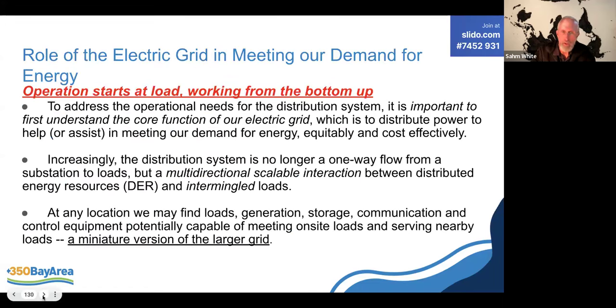Operation starts at load, working from the bottom up. To address the operational needs of the distribution system, it's important to first understand the core function of our electric grid, which is to distribute power to help meet demand for energy equitably and cost-effectively. Increasingly, the system is no longer a one-way flow from substations to load, but a multi-directional, scalable interaction between energy resources and intermingled loads. At any location, we may find loads, generation, storage, and communication control equipment potentially capable of meeting on-site loads and even serving nearby loads—a miniature version of the grid itself.